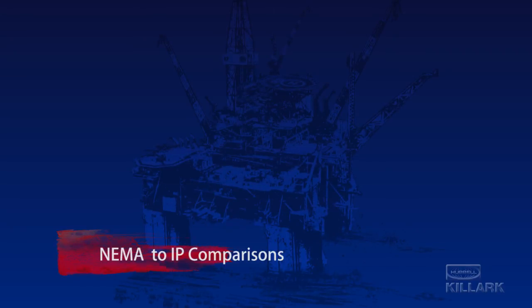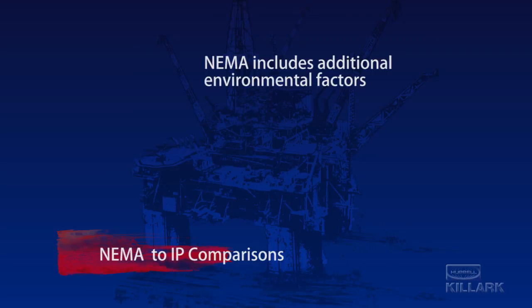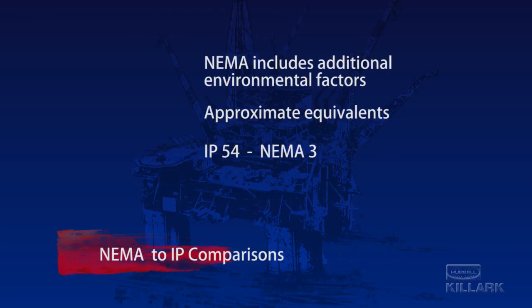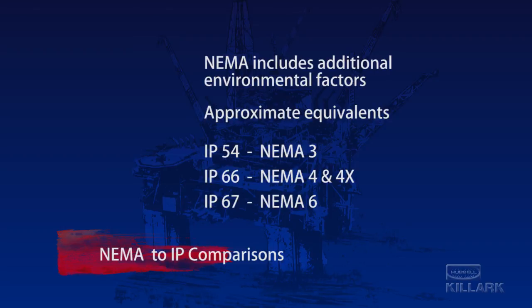Because the laboratory testing is not identical, and NEMA includes additional environmental factors, it isn't possible to exactly match NEMA protection types with IP ratings. But as a rough equivalent, the IP54 safeguards would be similar to NEMA 3, IP66 to NEMA 4 and 4X, and the IP67 would parallel NEMA 6.